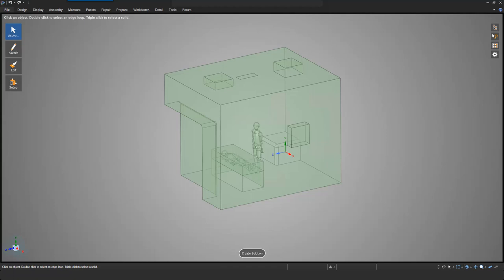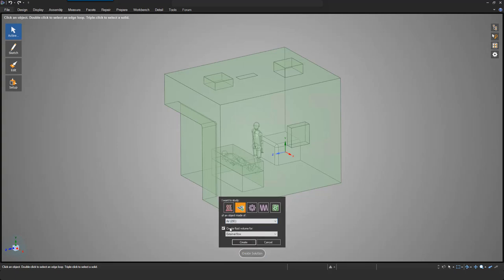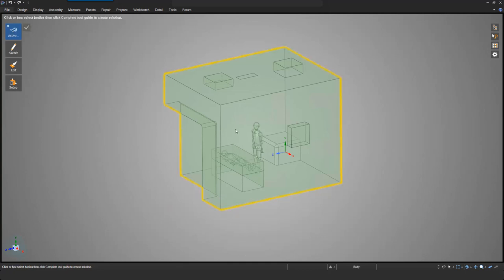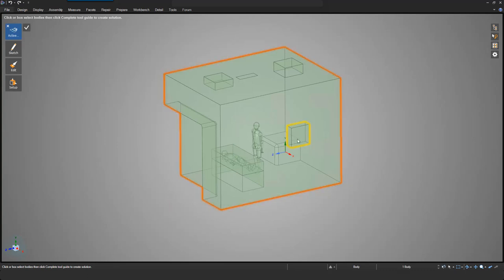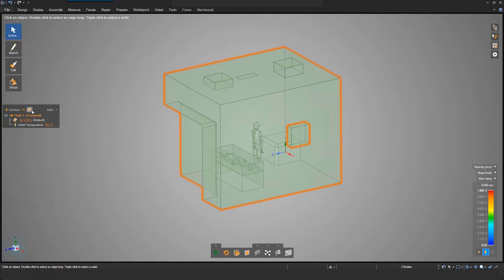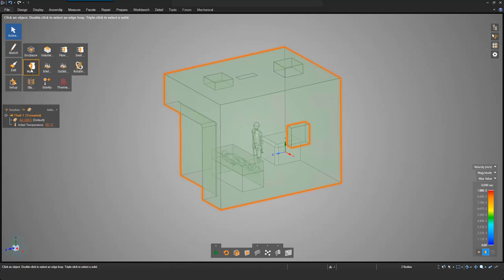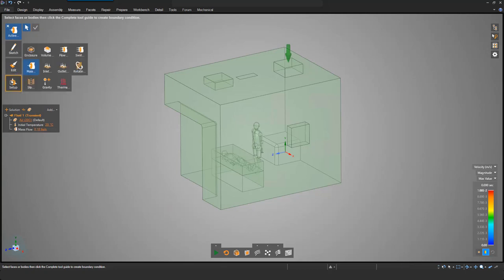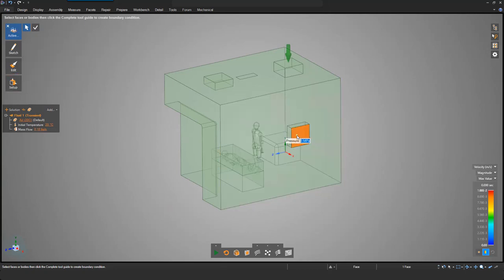I have already imported my hospital room geometry into Discovery Live. I start by creating a solution for the fluid flow — my geometry is the fluid volume, so I don't need to create it separately. I select the bodies I want to include in the simulation: the main room body and the ventilation exhaust for design one. Then I apply boundary conditions: a mass flow rate of 0.18 kg per second, and an outlet pressure of 0 Pascal.